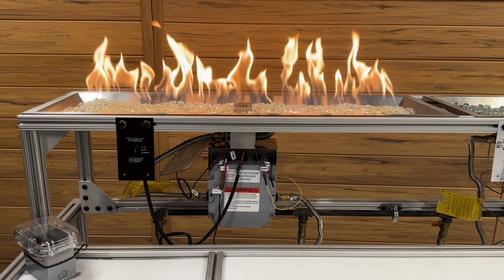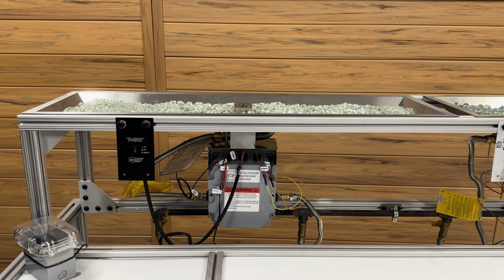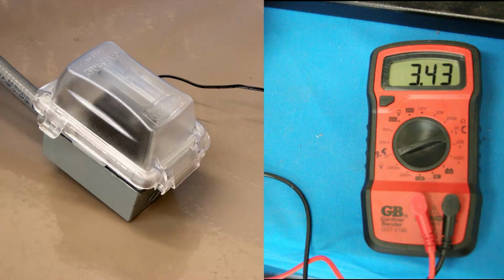Now, let's look at the scenario where the flame stays on beyond the ignition cycle, but will eventually shut itself off. In addition to validating the last three steps, also look for the following. If there is a consistent, strong enough wind, it is possible to blow the flame away from the sensor. If this happens for more than 12 seconds, the unit will go into shutdown mode. Lastly, it is also possible that your unit is shutting off as a result of inconsistent power supply. Your transformer needs to consistently put out 3.3 volts or higher. If this isn't happening, consider ordering a new transformer.